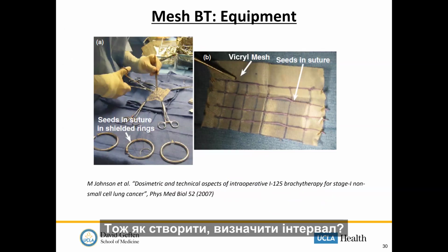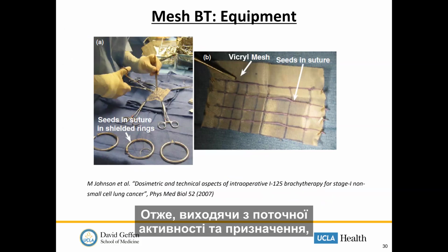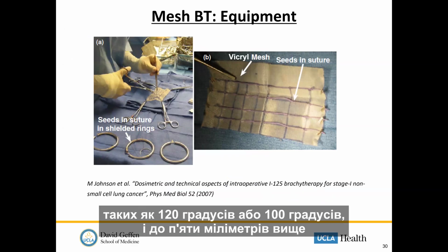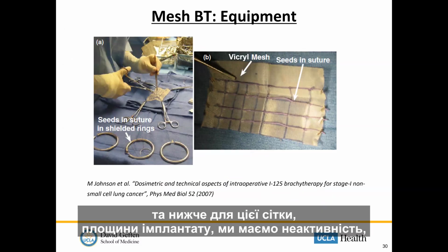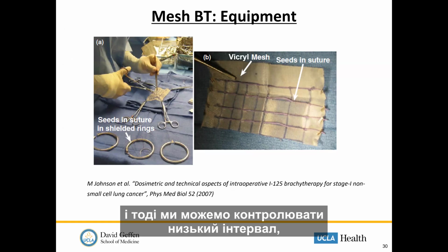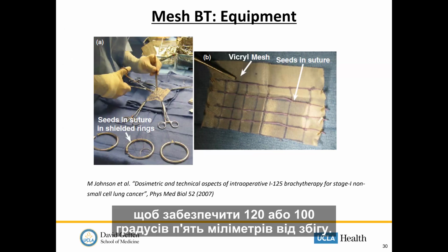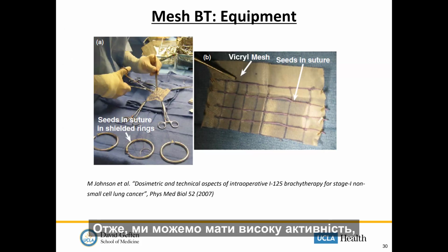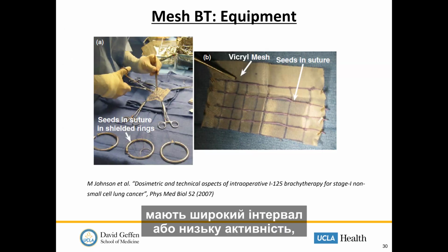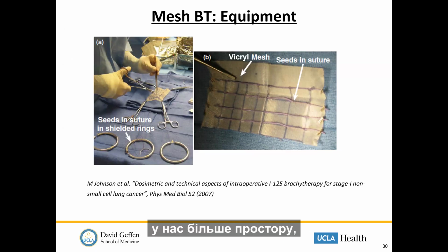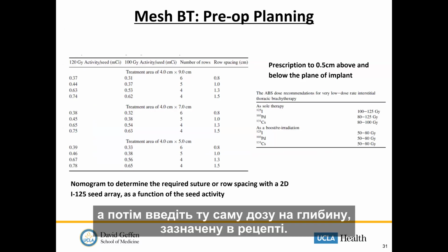So how do we determine the spacing? Based on the current activity and the prescription dose, like 120 gray or 100 gray, at 5 millimeter above and below the mesh, the plane of implant, and with known activity, we can control the spacing to deliver 120 or 100 gray to 5 millimeter from the mesh. So with high activity we can have wide spacing, or with low activity sources we have less spacing, and deliver the same amount of dose to the prescription depth.